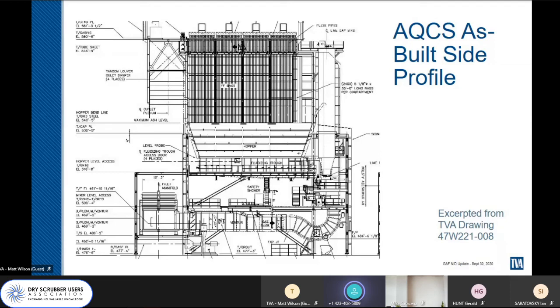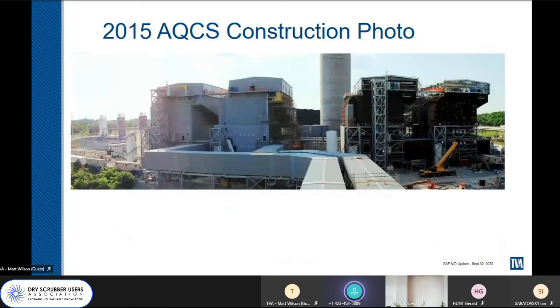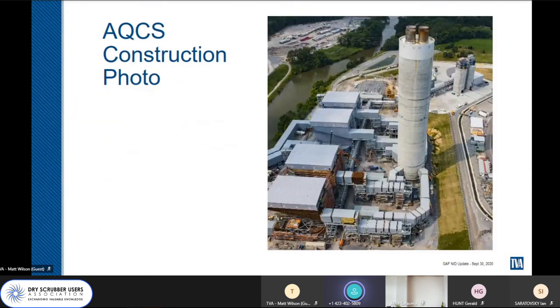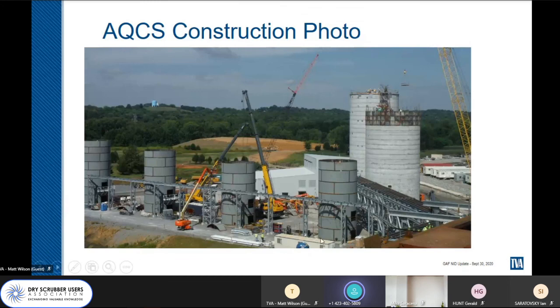For us, we ended up with 4 total silos up there that we showed earlier, and 2 silos supply 2 units. Basically, they are cross-tied. Only one is the normal feed for each unit, but they are cross-tied. Each of them is around 10,000 cubic feet. It's sized to store 30 hours worth of pebble lime at a 75% PRB, 25% Illinois Basin blend.